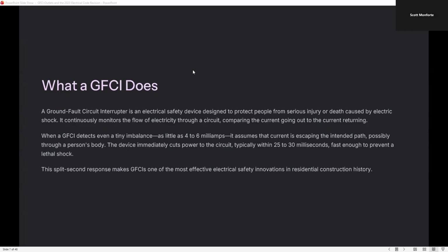A ground fault circuit interrupter is an electrical safety device designed to protect people from serious injury or death caused by electrical shock. It continuously monitors the flow of electricity through a circuit, comparing the current going out to the current returning. When a GFCI detects even a tiny imbalance, as little as 4 to 6 milliamps, it assumes that the current is escaping the intended path, possibly through a person's body. The device immediately cuts power to the circuit, typically within 25 to 30 milliseconds, fast enough to prevent a lethal shock. This split-second response makes GFCIs one of the most effective electrical safety innovations in residential construction history. So it's going to detect that interrupted supply of the power through moisture.